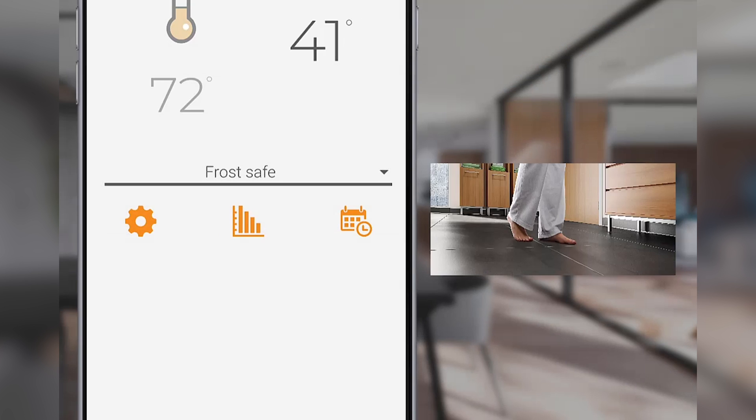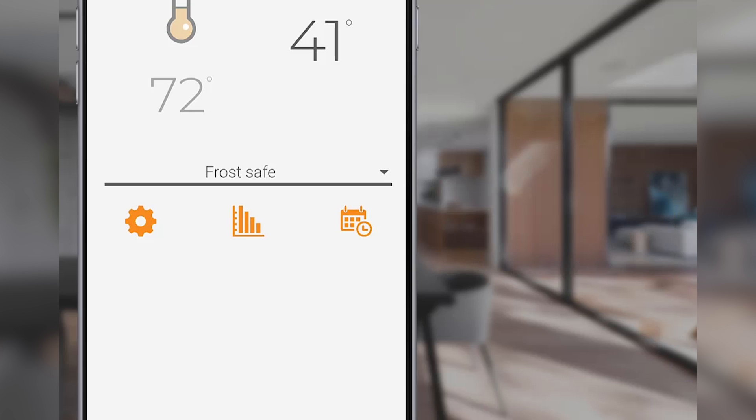Frost Safe mode ensures the floor's temperature doesn't drop below a minimum user-defined temperature. In this mode, the temperature is selected under the thermostat's device settings. If no minimum temperature is set, it will default to a temperature of 41 degrees Fahrenheit or 5 degrees Celsius.